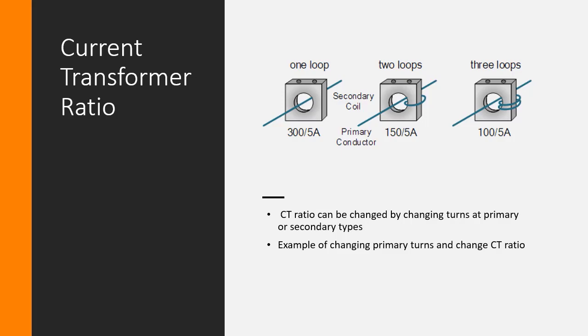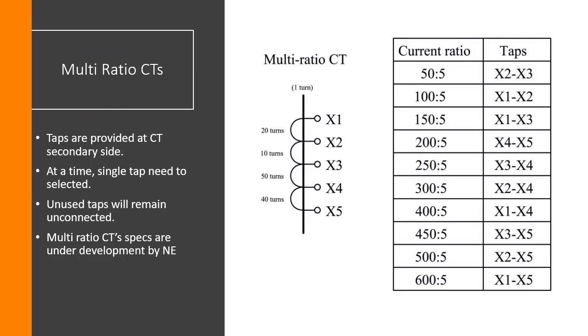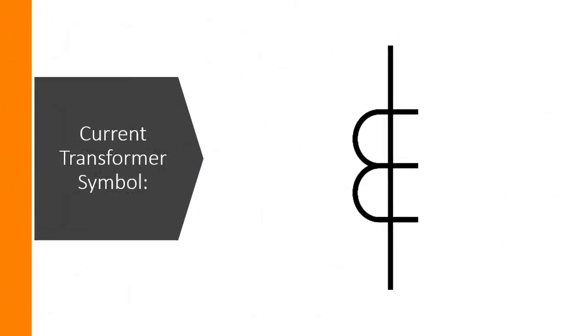This is an example of multi-ratio CTs. We have to understand that at a time we can only select one tap, and the unused taps will remain unconnected. They won't be connected or shorted. In multi-ratio CTs being developed, the taps are available on the secondary side only. CT selection and number of taps and turns selection are made on the secondary side.